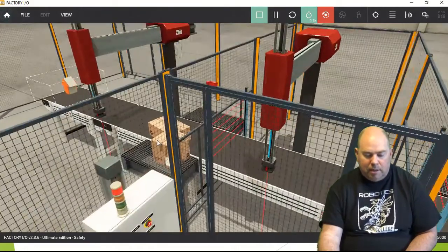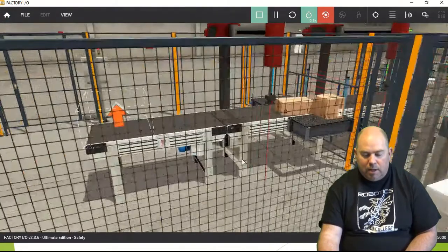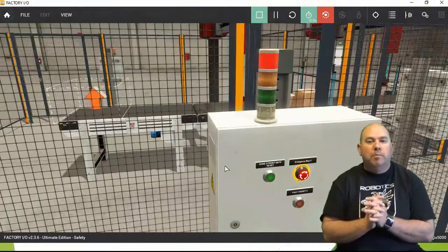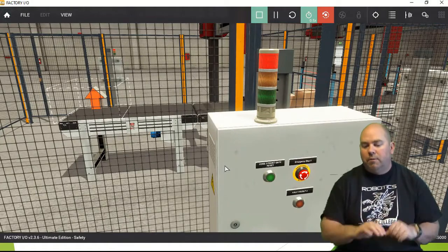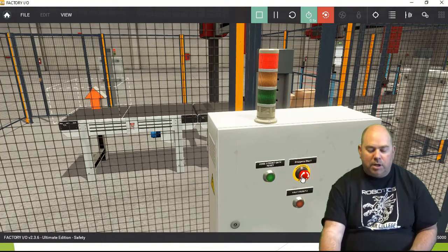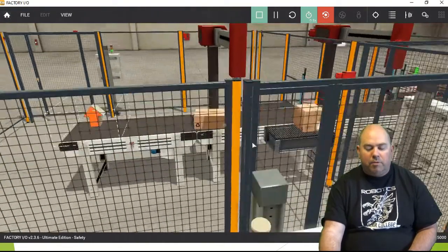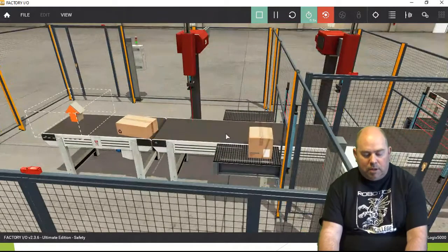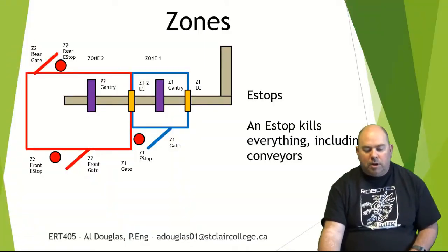E-stops kill everything, and that is pretty typical for machines — if you press an e-stop button anywhere on a machine, that's going to kill everything in sight. I pull that e-stop back out and the machine doesn't start automatically. I actually need to push the blinking green reset button for things to start back up again — and then off they go. E-stops are going to kill everything in our system.